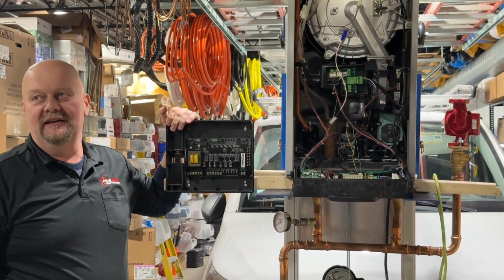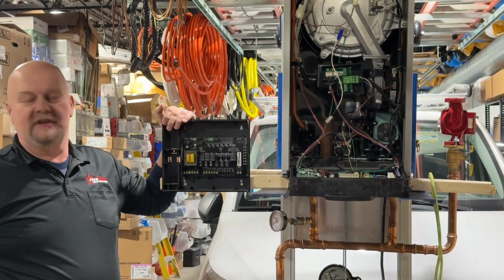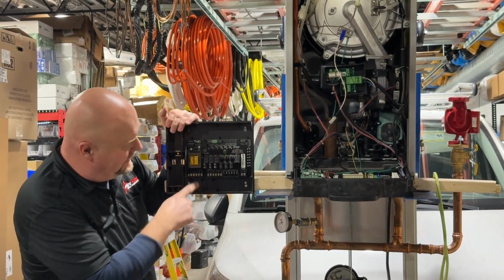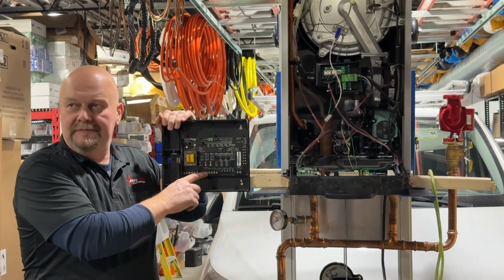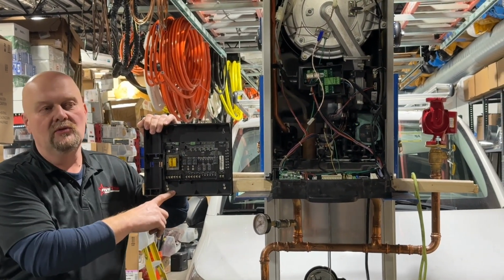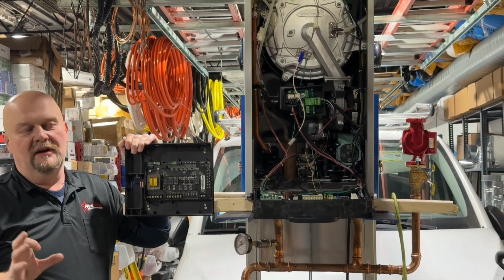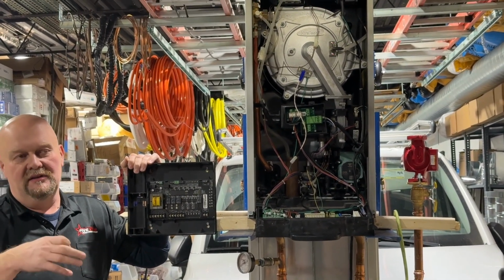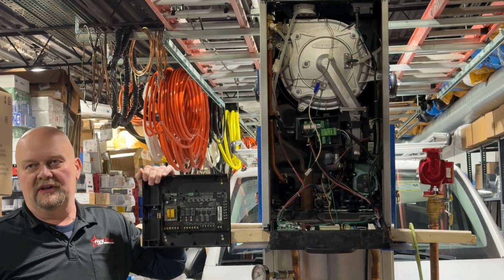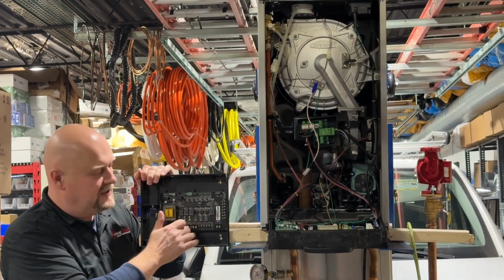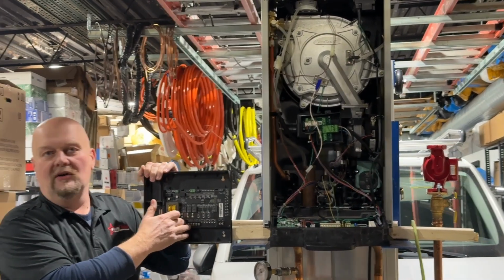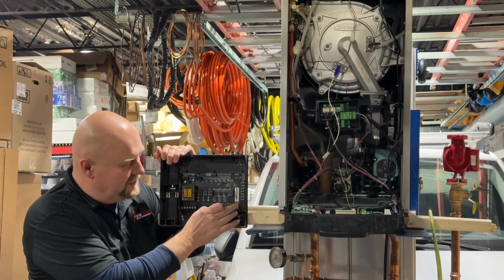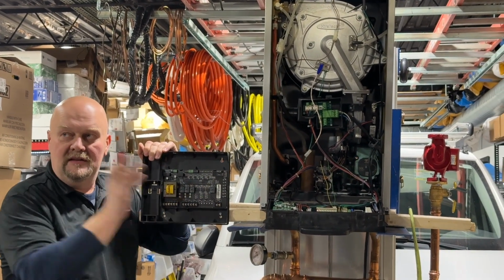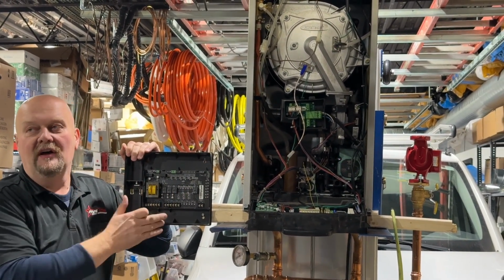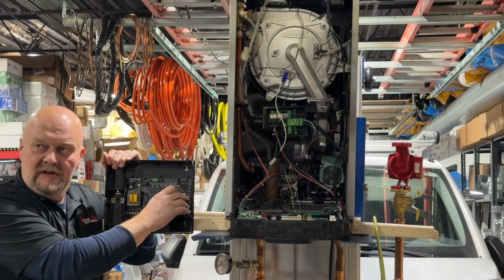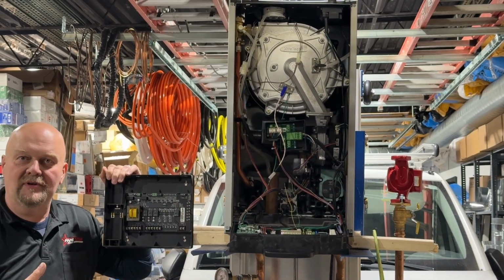I'm glad that Taras found that, but you learn things from mistakes. So anyway, a lot of these controls have a primary pump, and the primary pump is designed to heat up a storage tank, basically to engage a pump that heats up a storage tank. And there's usually a switch that tells you if pump one is a primary pump, or there's a separate one for primary. This one actually is a little different. This one is separately done here, which is better. The other one had 1, 2, 3 pumps, and one was primary, and there was a dip switch that was meant to be turned off if you don't want it to be a primary pump.